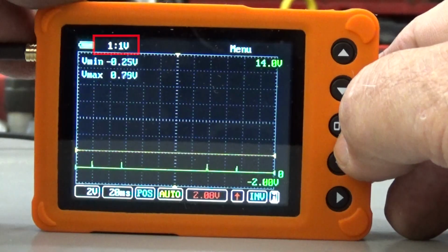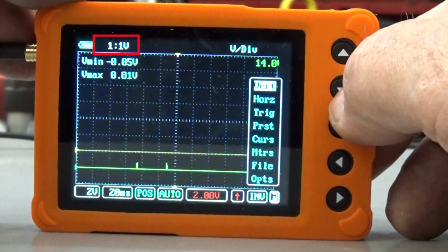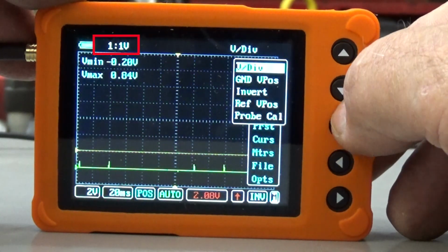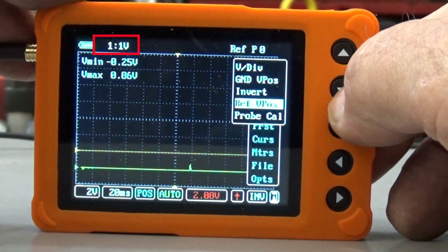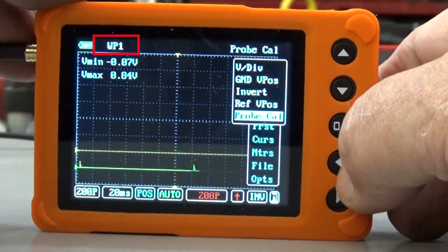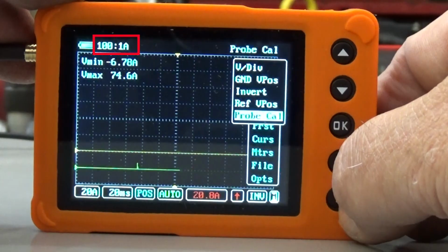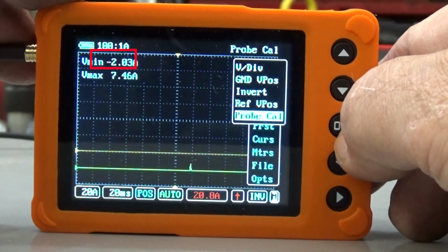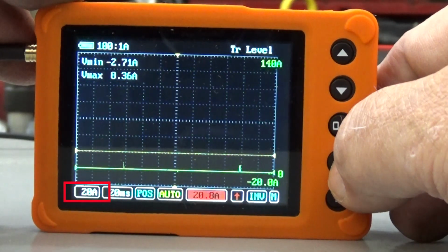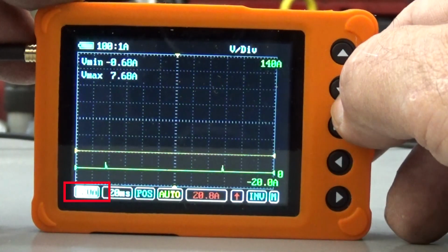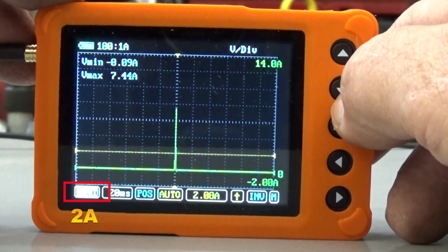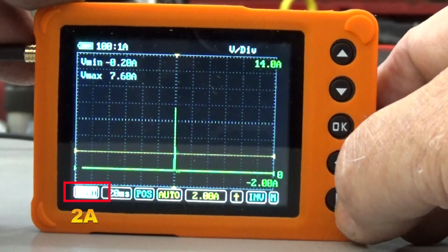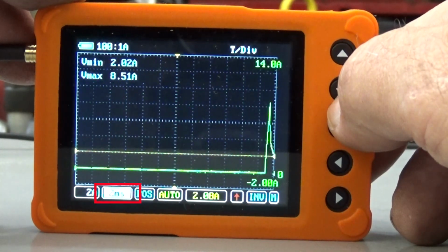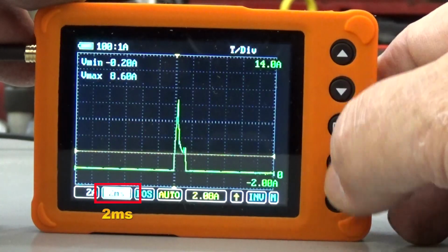First, I'm going to change the probe to 100 to 1 amps by navigating to the menu, vertical, and probe calibrations. Use the left and right arrows to select 100 to 1 amps and press OK. Second, navigate to the amp vertical scale and use the up and down arrows to change the settings to 2 amps per division. Third, navigate the time or sweep setting to change that to 2 milliseconds per division.